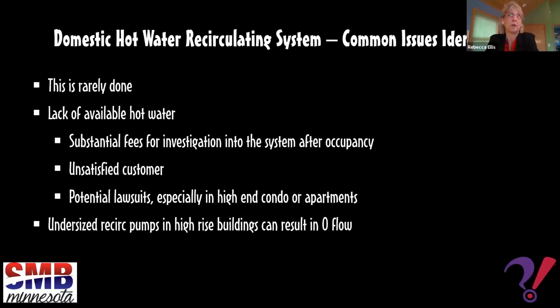So we're often called into buildings that are pretty new, where owners aren't getting the hot water when and where they need it. We find flow is going, the hot water is being maintained, to the units closest to the pump, and no flow to the units furthest from the pump. That's so easy to figure out if you just plot out where the complaints are coming from. We also see many times pumps are insufficiently sized to push the water through the piping.